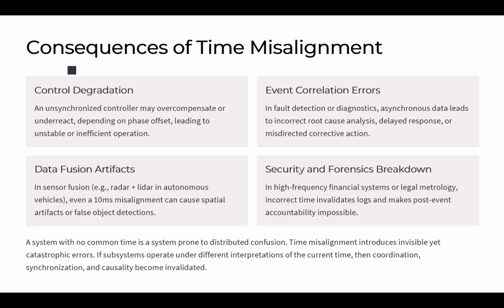Or when we talk about event correlation errors, for example, in fault detection, logs from different devices must be temporally aligned. So the time should be aligned. If one sensor, for example, logs an overcurrent at a time and another logs a relay trip at a non-aligned time, were these events related? Without synchronized time, the answer is basically ambiguous. So we cannot follow the causality of the events, when the overcurrent happened and when the relay tripped.